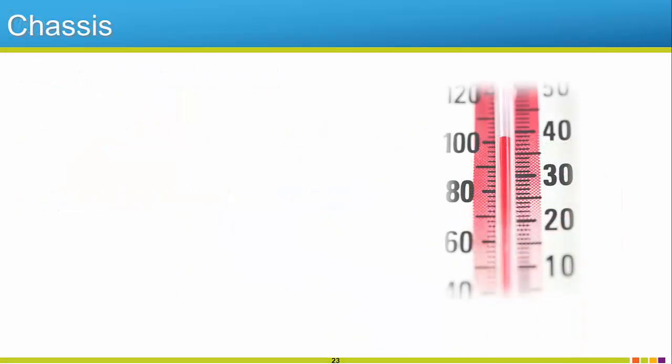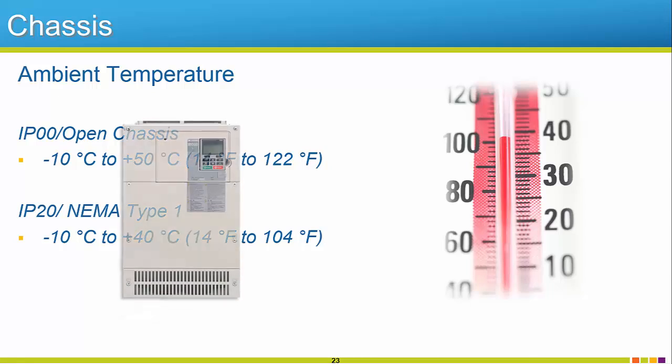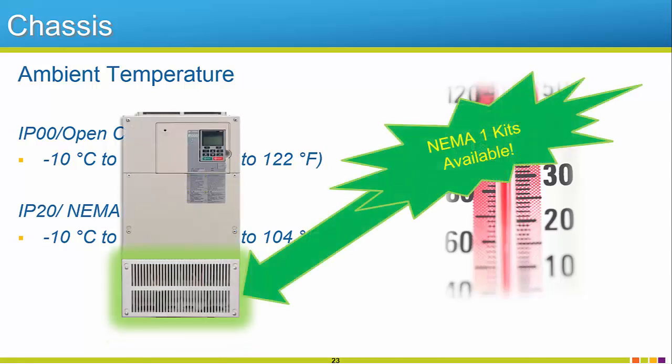The R1000 comes in both open chassis and NEMA Type 1 enclosures. The IP00, or open chassis type units, can operate in an ambient temperature of minus 10 degrees to 50 degrees Celsius. The IP20, also known as NEMA Type 1 chassis units, have an ambient temperature range of minus 10 degrees to 40 degrees Celsius. Additional environmental specs can be found in the R1000 technical manual. Is a NEMA 1 type enclosure a necessity? Well don't worry, because NEMA 1 kits are available for all open chassis units.